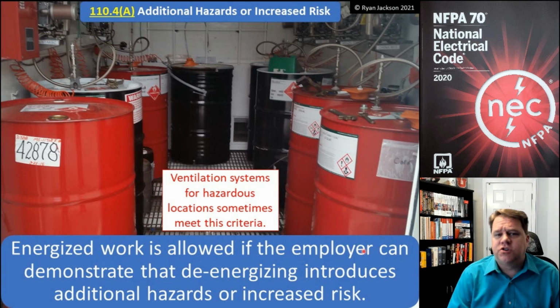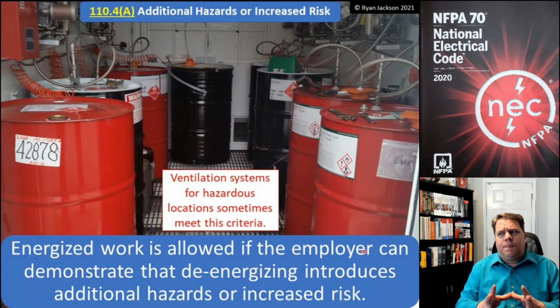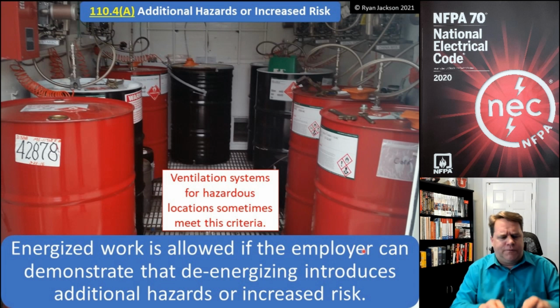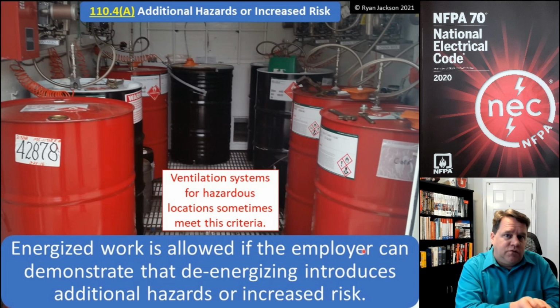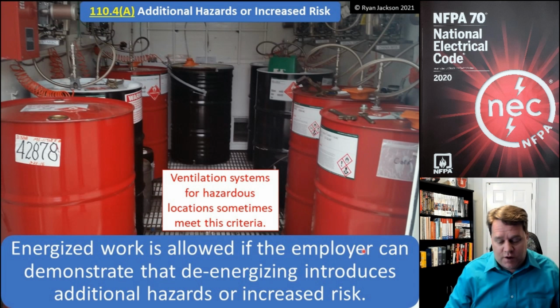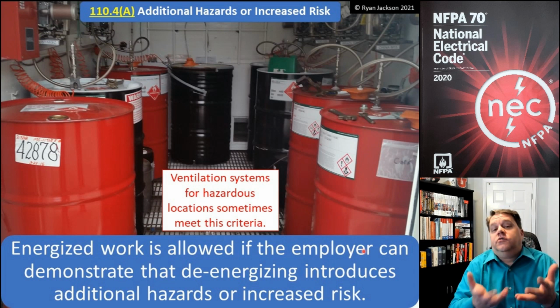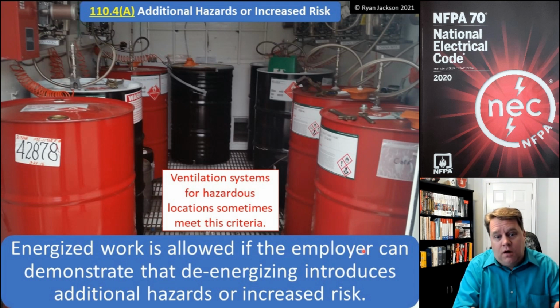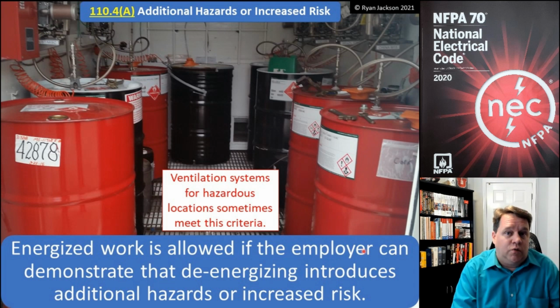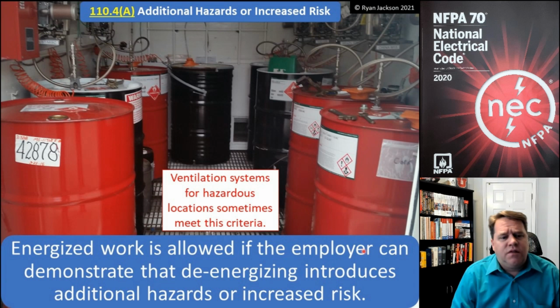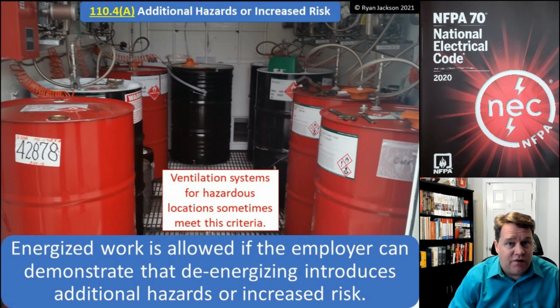Now, when we say additional hazards or increased risk, well, an increased risk from what? We're increasing it. So what was the initial risk that we're increasing? Well, the initial risk of working energized is you dying. So an increased risk, a worse risk than you dying, would have to be demonstrated in order to allow you to work on energized equipment. This is something that really shouldn't happen very often. So an increased risk or actually introducing additional hazards does allow me to work energized.